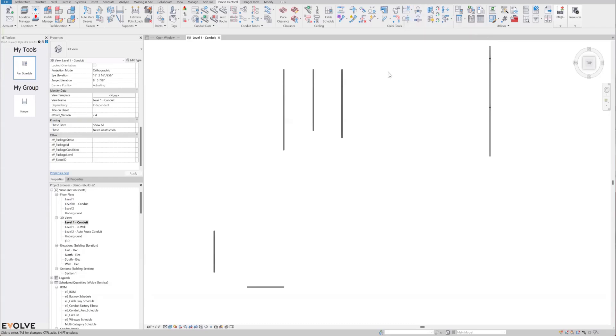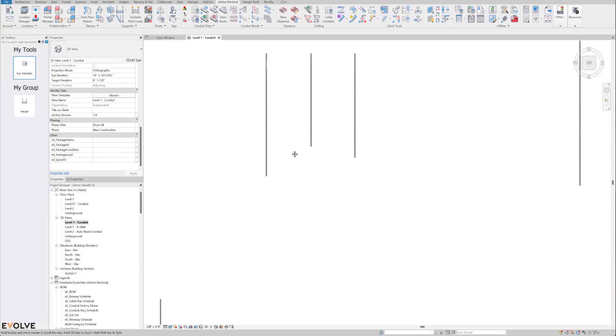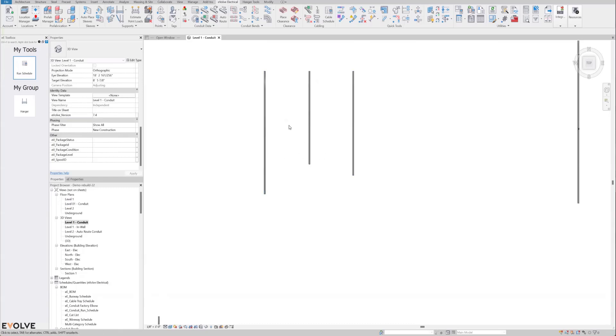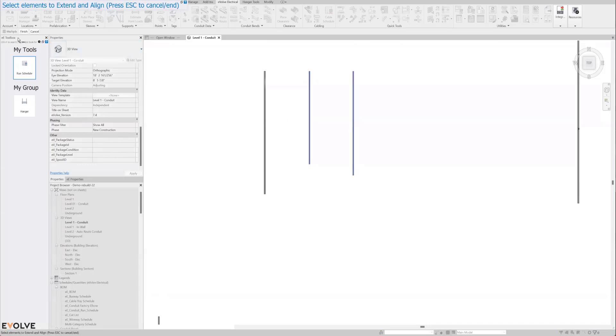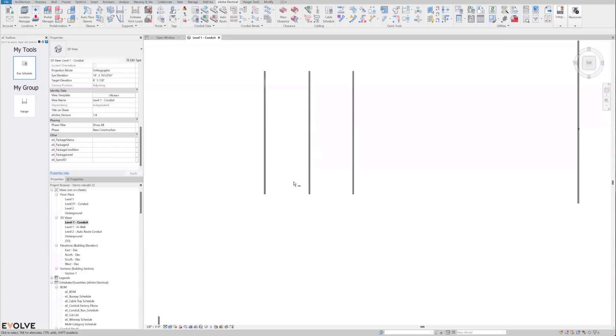With extend and align, a good use case is this example where you have some different pieces of conduit that are not aligned at the end. You can select the tool, select the end of one of your runs, and then select the other conduit you want to align to and click finish. It will then extend and align all of them. There's also the option to move and align as well, so instead of just extending, you can actually have the conduit move if you wanted.